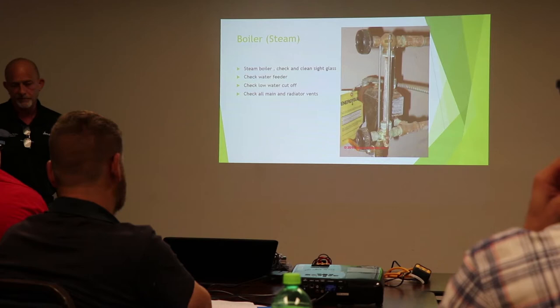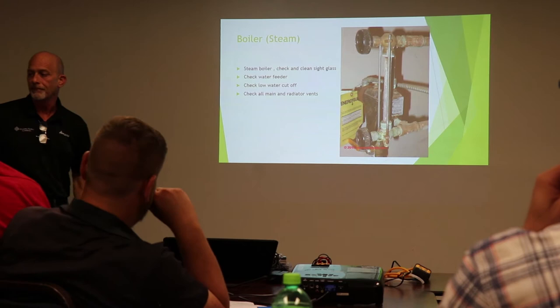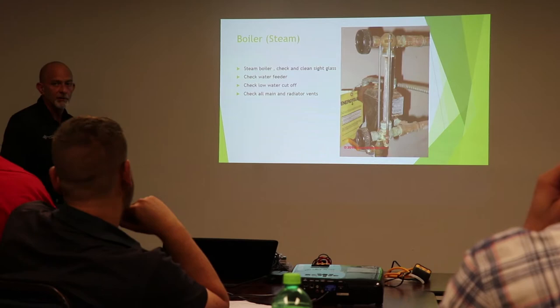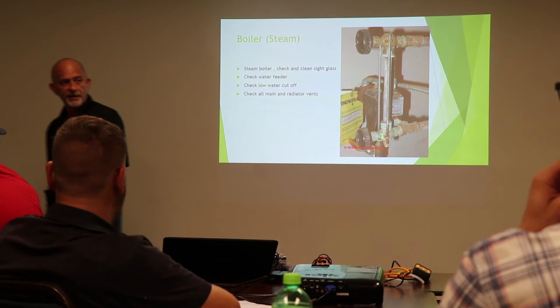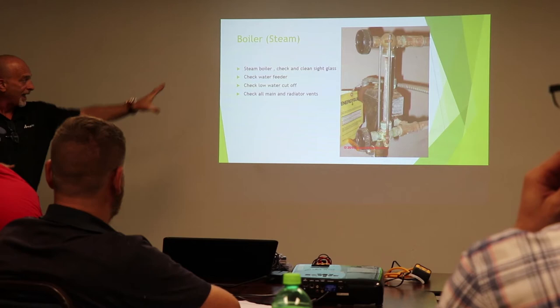Make sure it looks brand spanking new before we put it back in. Steam boilers. How many guys in here work on steam? We talked a little before everybody got here. Steam is few and far between, but there's still steam boilers out there. Biggest thing on a steam boiler, you want to make sure you clean the sight glass. Anybody ever pull one out to clean it? Be careful. That particular one there, you might have problems with pulling it out.